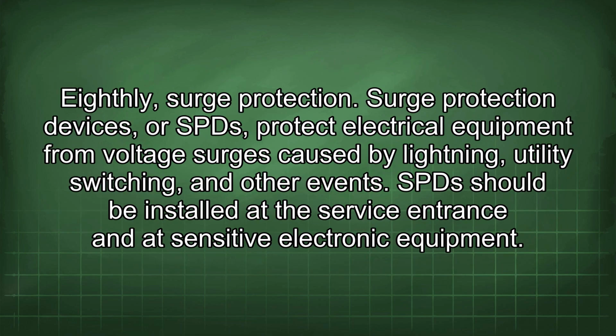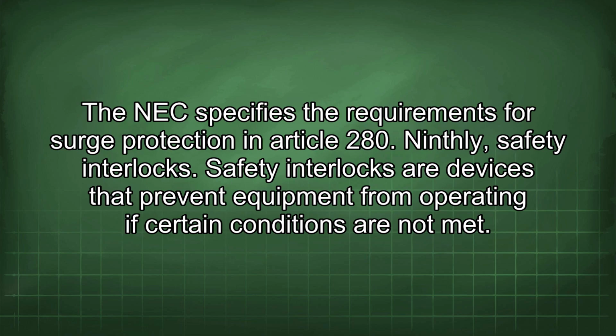Eighthly, surge protection. Surge protection devices, or SPDs, protect electrical equipment from voltage surges caused by lightning, utility switching, and other events. SPDs should be installed at the service entrance and at sensitive electronic equipment. The NEC specifies the requirements for surge protection in Article 280.